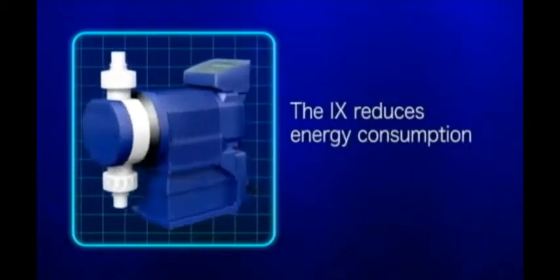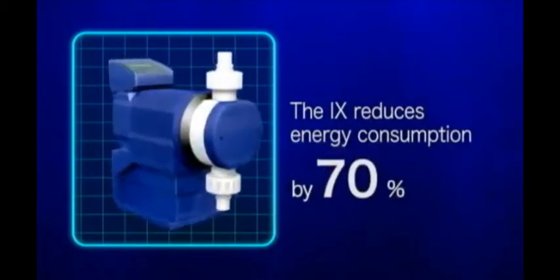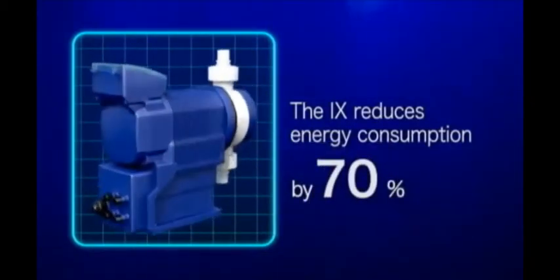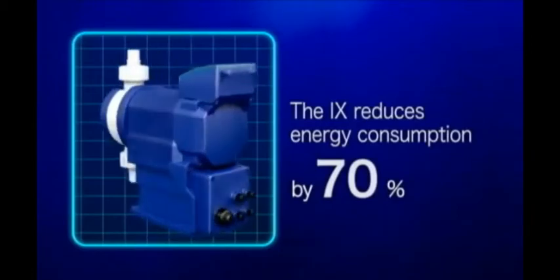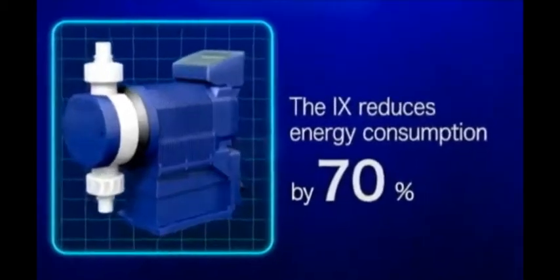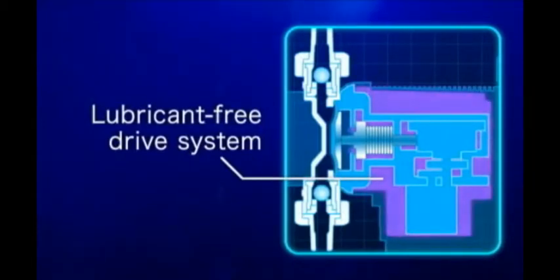A detailed analysis of the energy consumption of conventional dosing pumps led to the new high efficiency design that was implemented in the IX, resulting in a 70% reduction in energy consumption compared to conventional pumps. A unique lubricant-free drive system has been developed that eliminates any concerns about oil leaks and requires no maintenance.